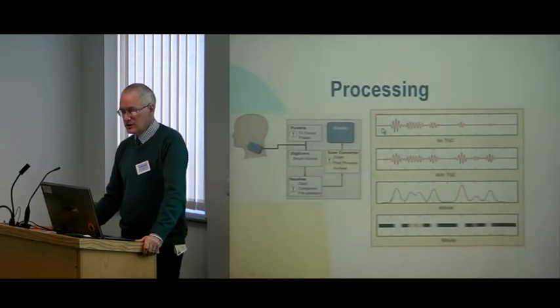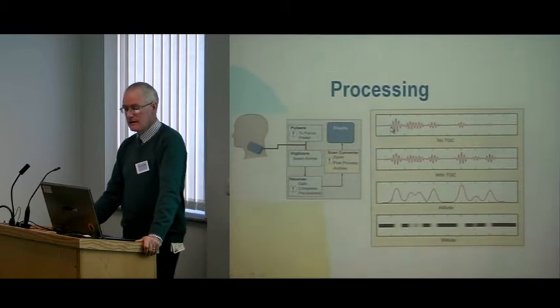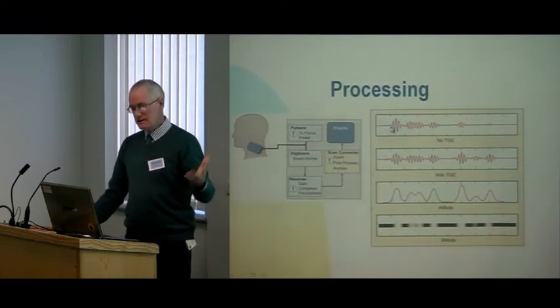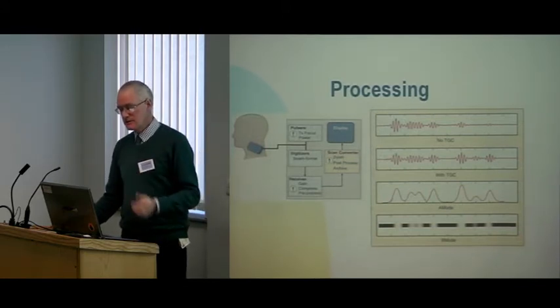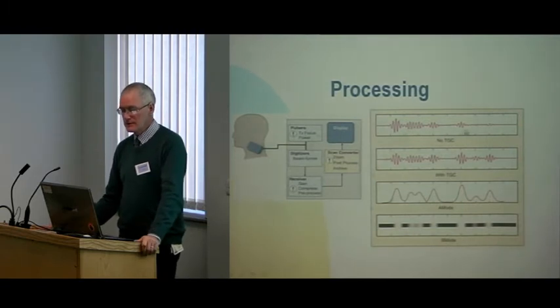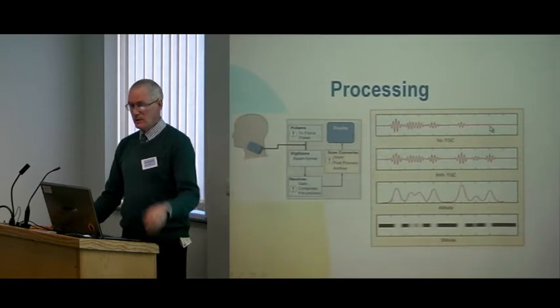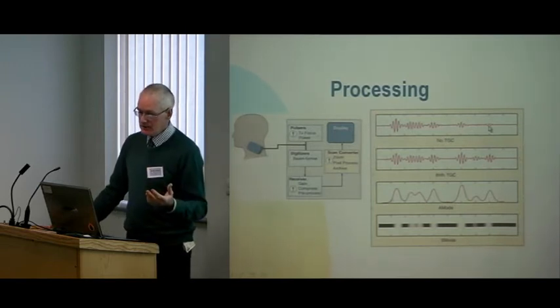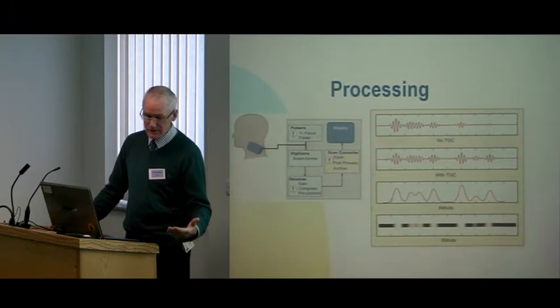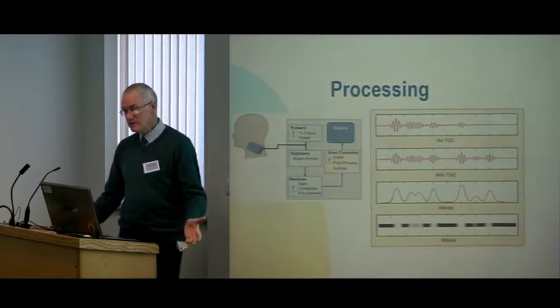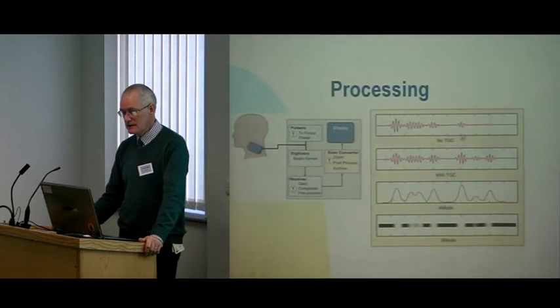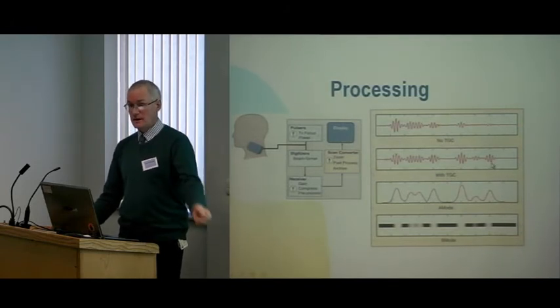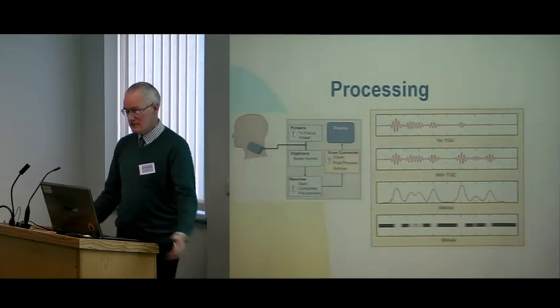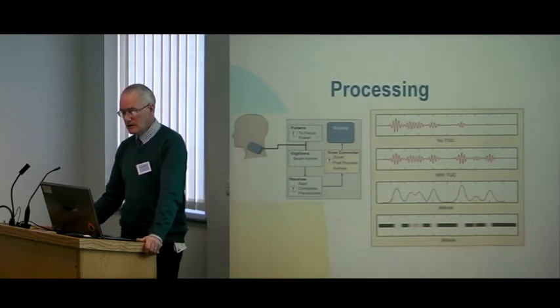Now the raw information that comes back from the patient, the sound that hits the crystals, as the crystals are deformed and produce an electrical current, this is the raw electrical current that comes back. Here at depth, you can see that the signal is very weak, very quiet at depth, so you would expect the image to be relatively difficult to see at depth. And what we need to do is to magnify those signals with the gain control, the far gain control, the distance gain control, and then modulate that with a computer.